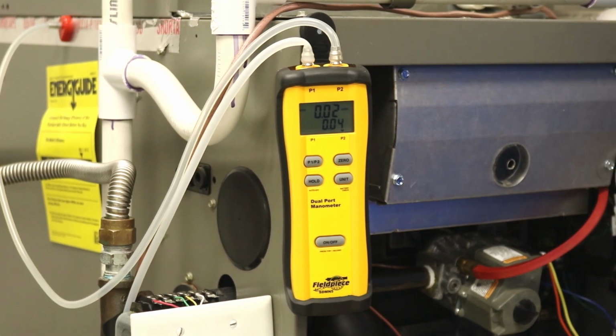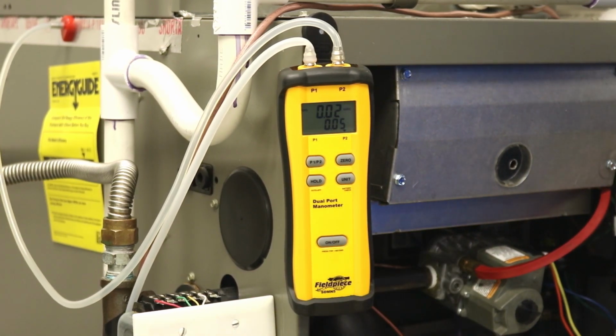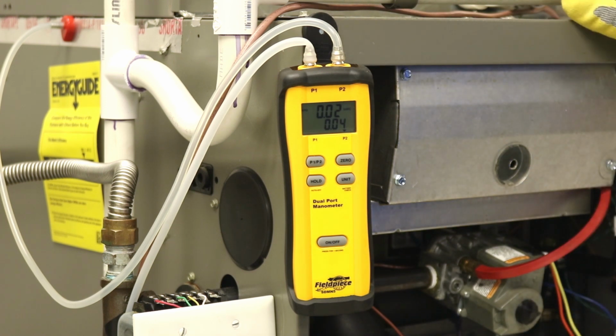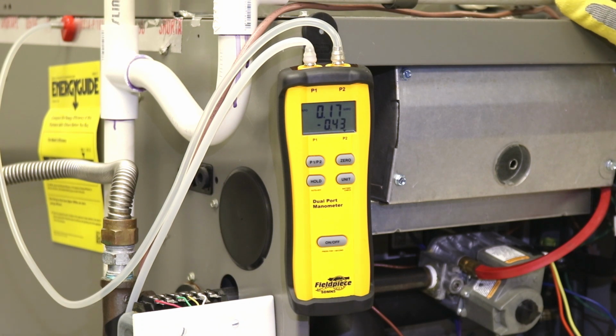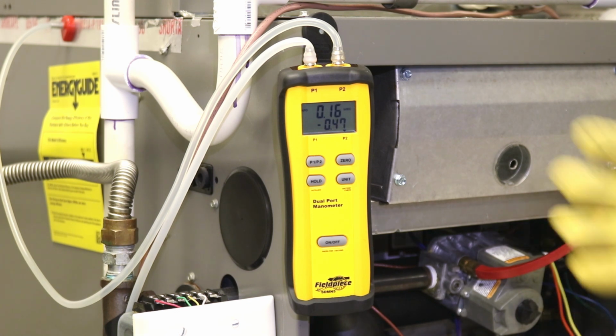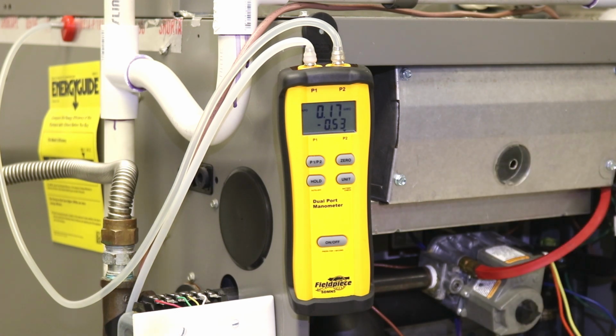So from this point, we're gonna turn the system on. We've got our manometer on already. Let's see what she has. Right now, the static pressure of this system, which for our purposes, we're in a lab here and don't have a lot of ductwork running to the system, and it deadheads right above the unit.